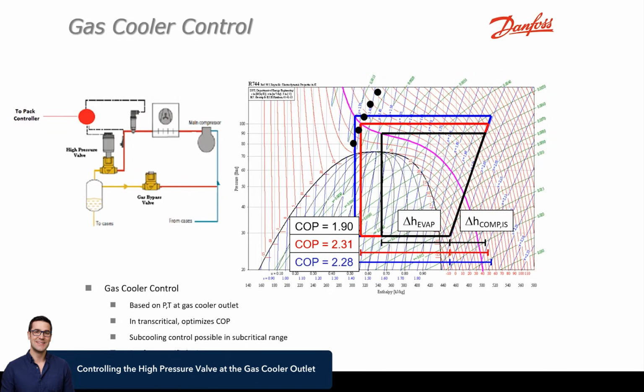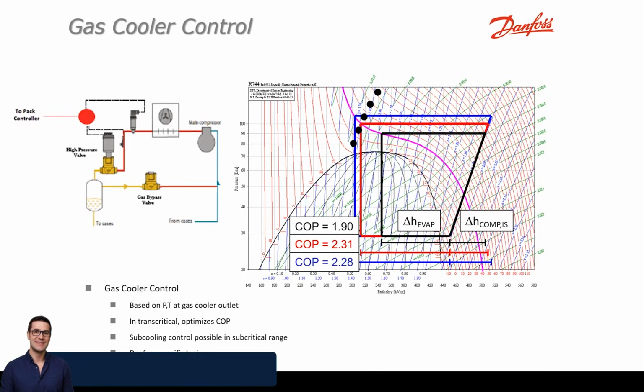Depending on how high you allow that pressure to build up in the gas cooler, you can allow it to build up at a lower level, but you don't get as much liquid back into the system for your cases. You can allow it to build up to a very high level, but then compression ratio and other things come into play. So yes, you get more liquid back into the system as an end result, but it takes a little more work to get there. And then you have what would be defined as an optimal setup, where maybe it's not the maximum amount of liquid you can get, but your compressors don't have to do as much work. So our controller tries to find that optimal point based on COP, and based on the temperature out of the gas cooler, we'll pick a specific pressure target for that high pressure valve and try to get there. Okay. And so this is only when it's in transcritical mode that it is acting like this?